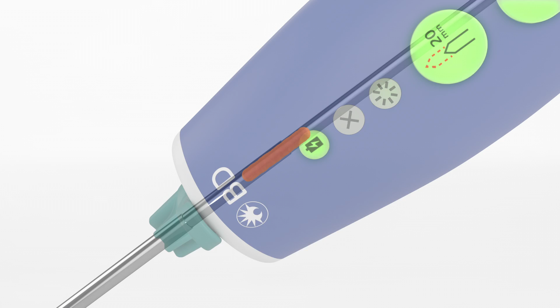The tissue sample, once obtained, is then transported to the sample container. Once you've collected the last tissue sample, you can detach the removable support cannula, leaving it in the breast to place a tissue marker. Then remove the probe and care for the incision site. To remove the sample container from the driver, turn the container counterclockwise. Then, open the sample container to remove the samples. Please note that the sample container is sized to fit a standard formalin cup.